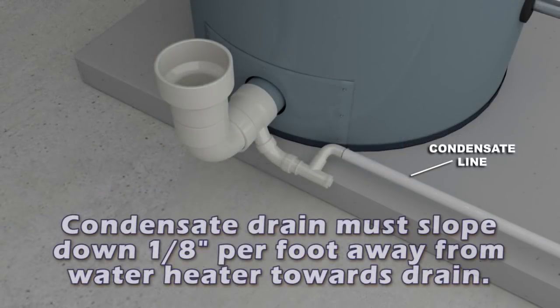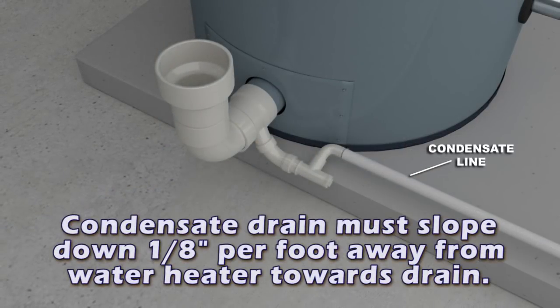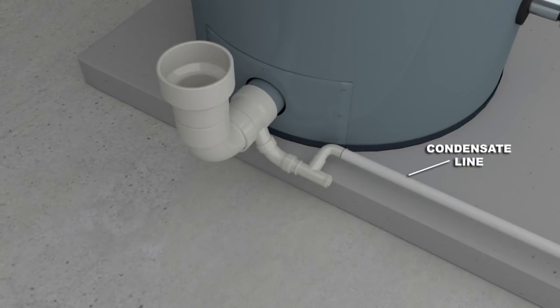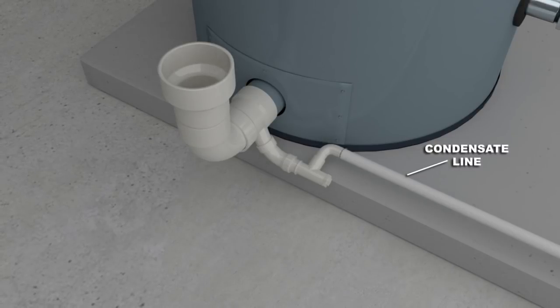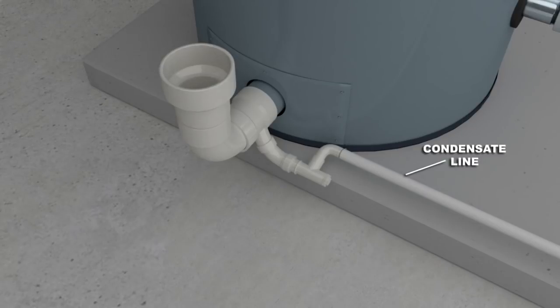The condensate drain must slope down 1/8 inch per foot away from the water heater towards the drain. The water heater may need to be elevated to ensure this slope. Prime the condensate trap to prevent flue gases from entering the room.